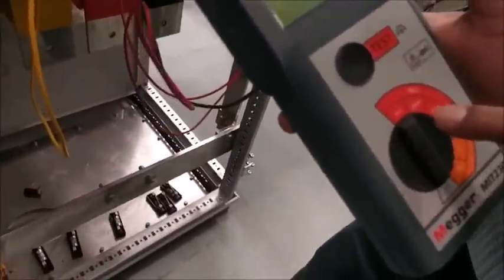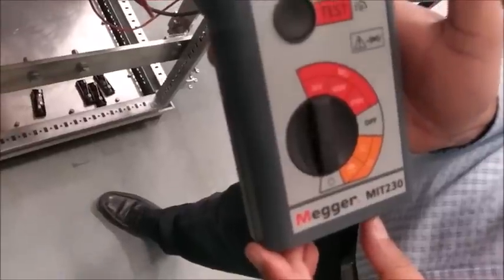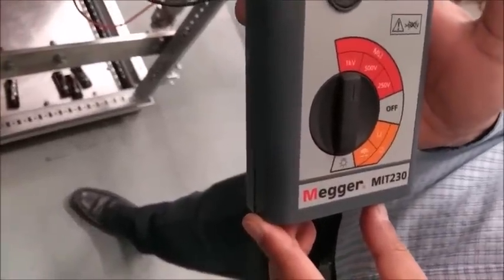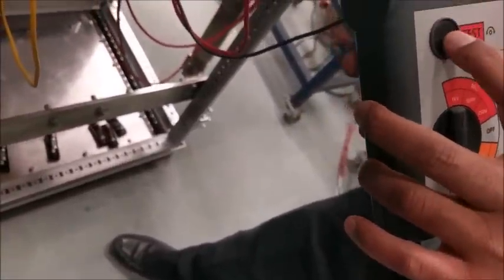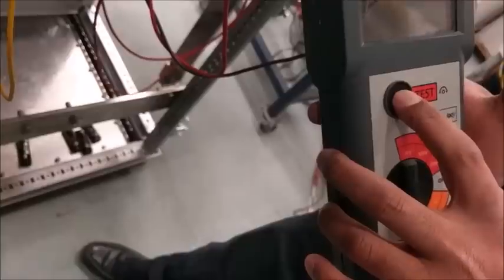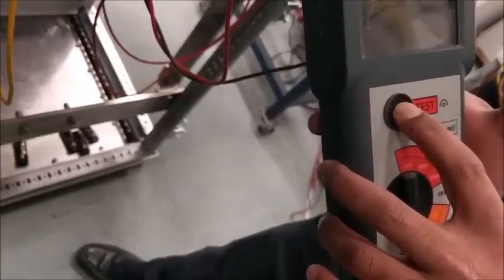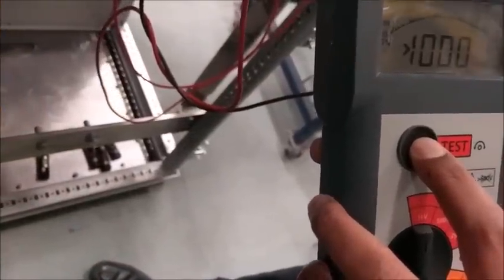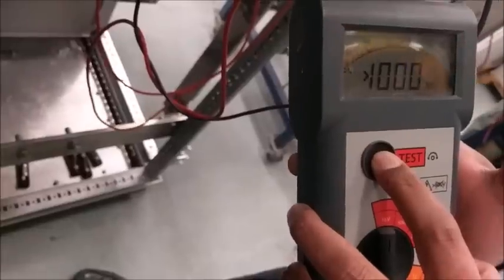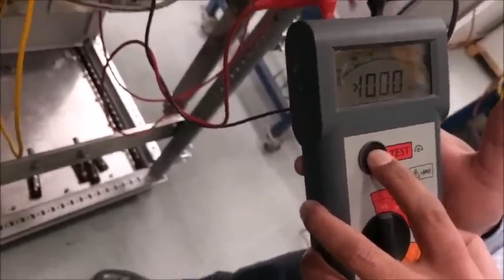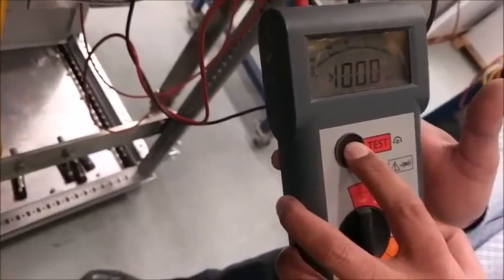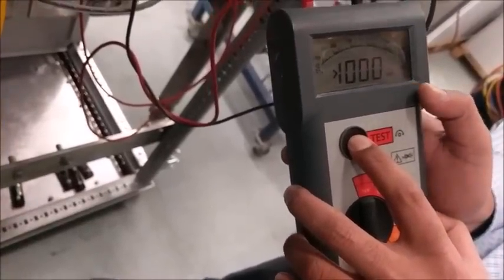Now I have to apply 1000 volt, 1 kV. This is a DC supply. Once I put the test on, it shows how much the ohm value is. Now it's above 1000 megaohm. Don't touch, sir. Don't touch. The supply is there.